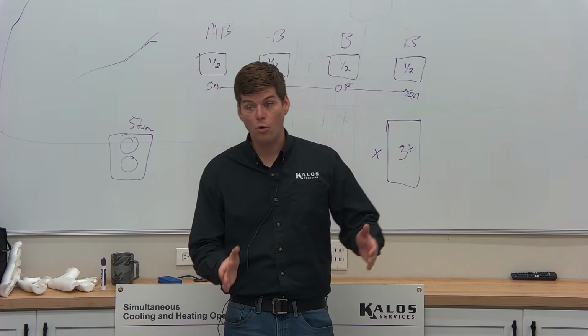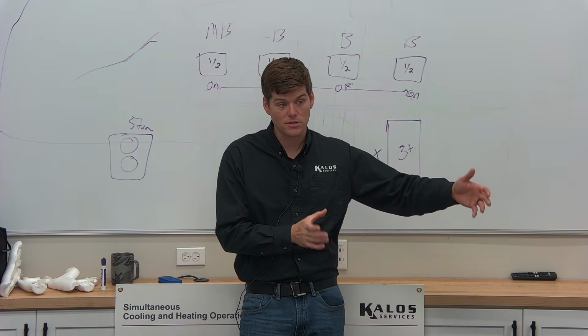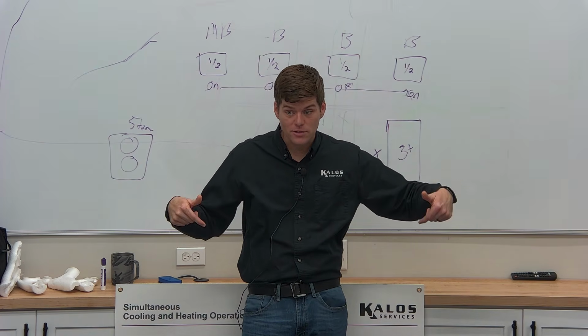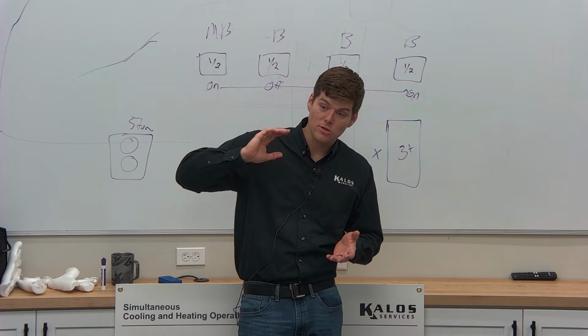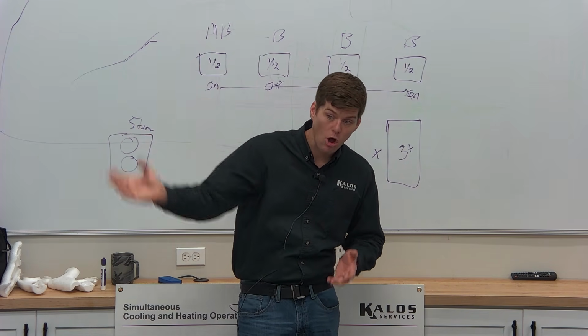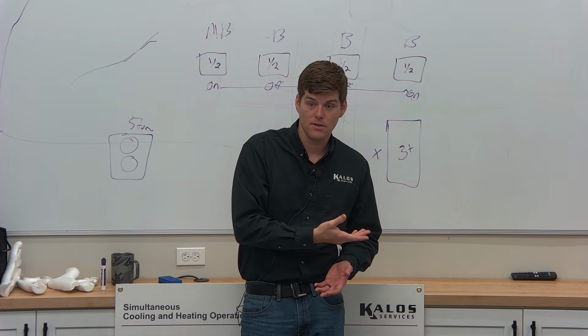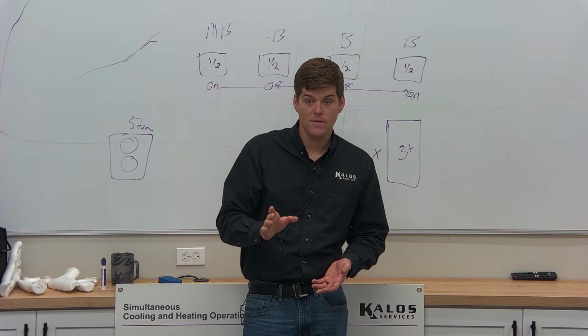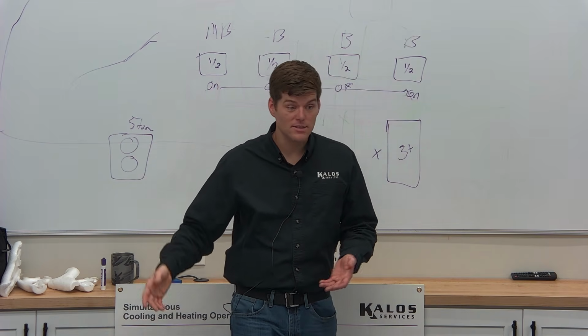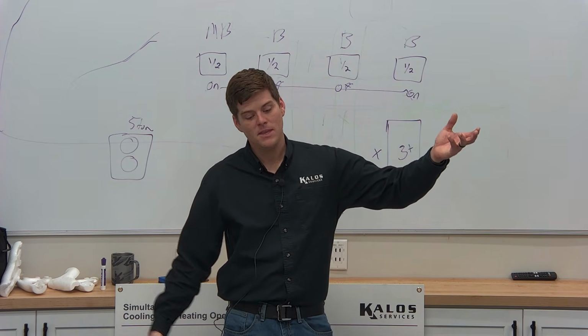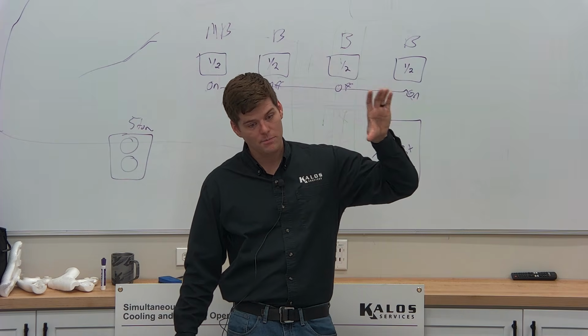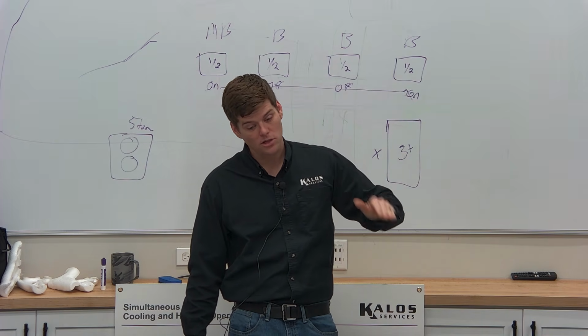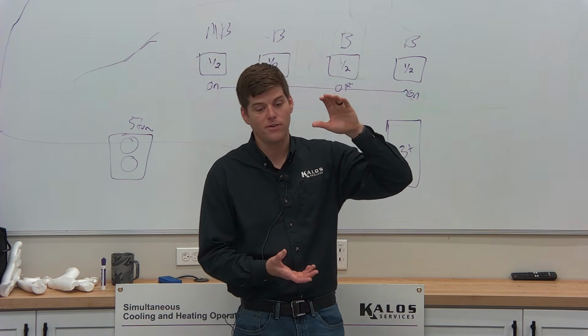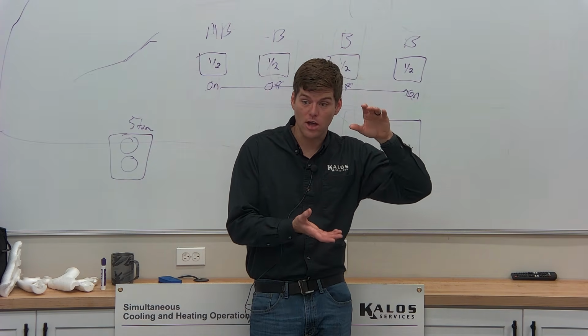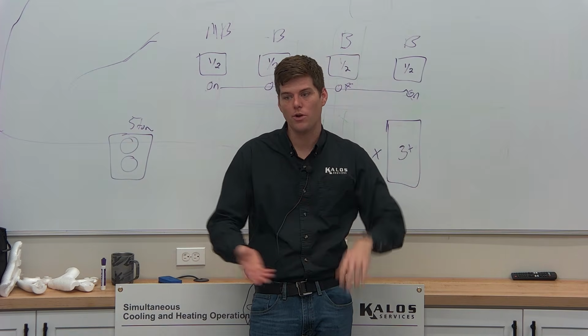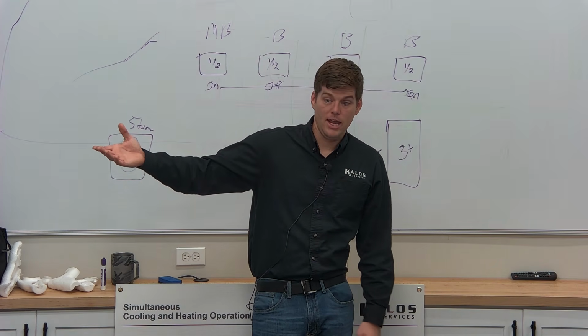And that's because we have oil return modes on these systems where the system will actually open its expansion valves, turn its fans off, and flush a large amount of liquid through all of its indoor units to bring all oil back at any given time. It does that automatically. And the calculation behind that is it takes compressor revolution speeds. It takes the knowledge and understanding in the programming that at each speed, how much oil is lost at that speed. It does a total calculation to find out exactly how much oil has been lost to say, oh, my compressor should be low on oil, go into oil return mode. It knows what it's doing.